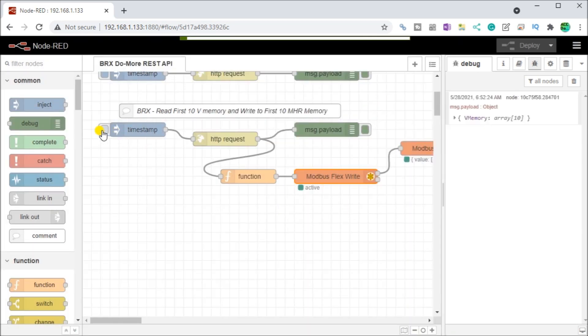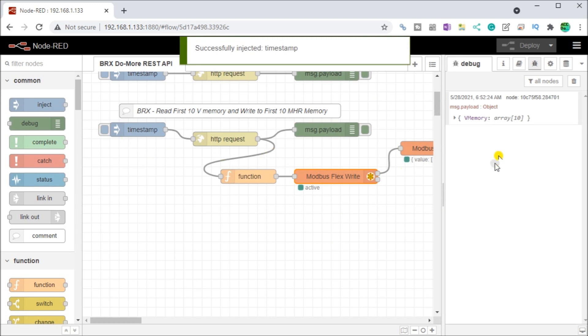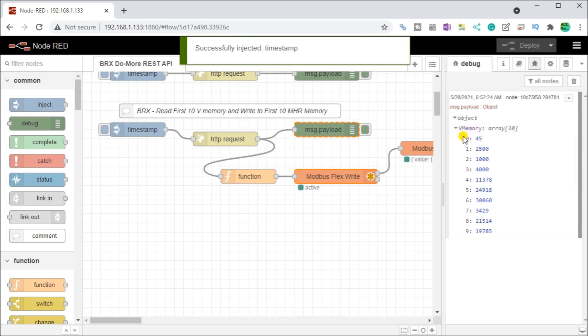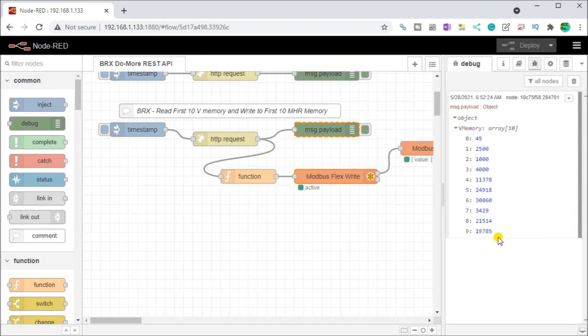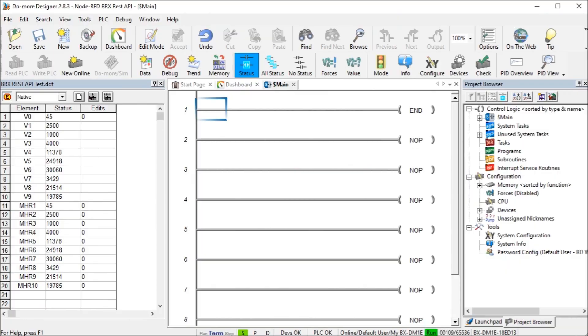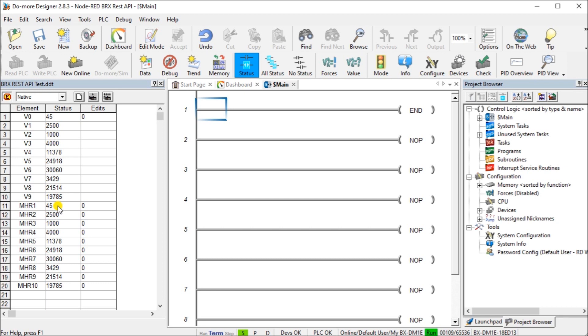What we're going to do is just hit send. And what you'll see here is there is my V memory area and there are my parameters. If I look at back to my do more, you can see here that here is my V memory area. They map directly to my MHR area or Modbus holding register area 1 to 10. So we're just copying those to here. Without any program that we have located in our controller.